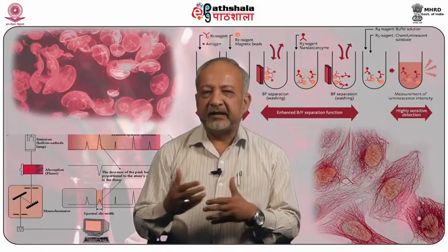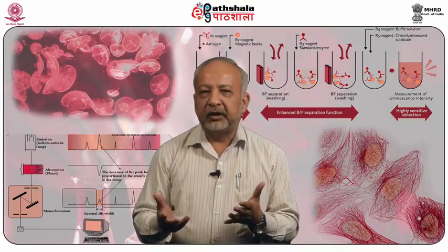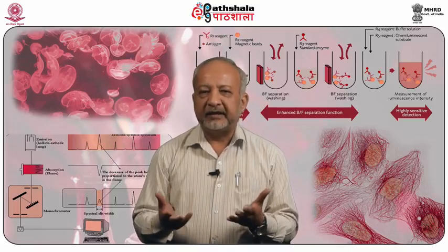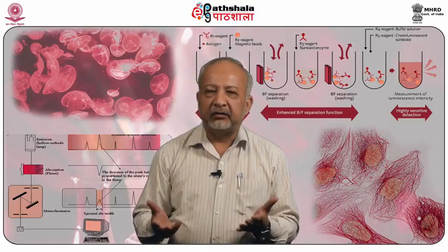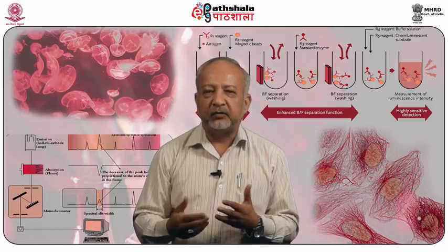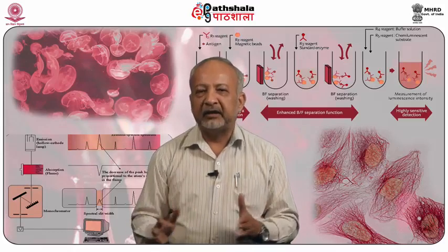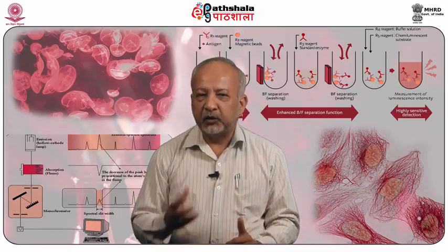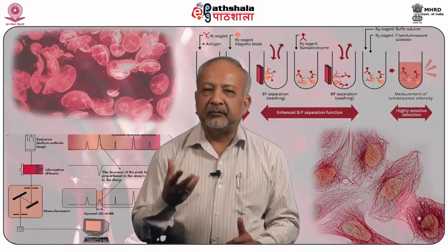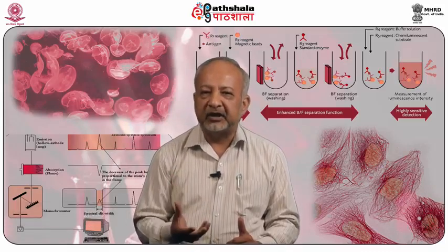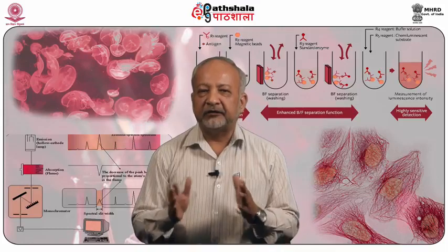Just to revise the previous module, you have inlet devices which depend on the nature of the molecule. You may have a direct probe, GC, or HPLC, and a modern mass spectrometer generally has more than one inlet device. The most important, again I am repeating, is the ion source, which depends on the nature of the sample.